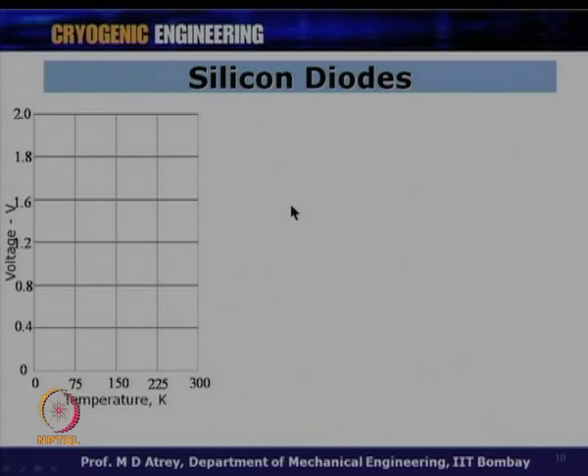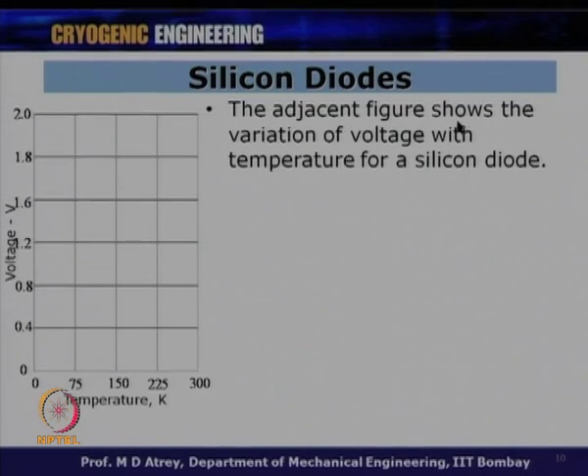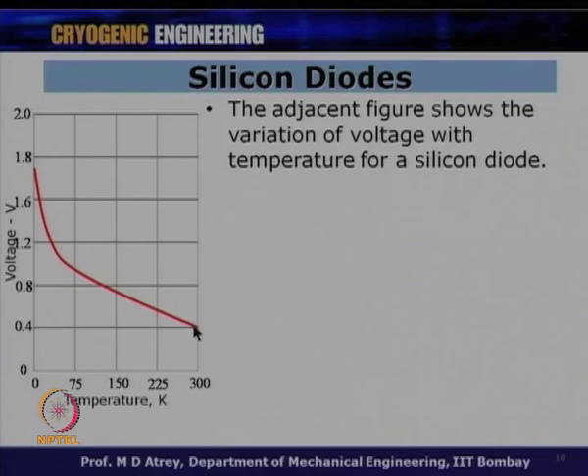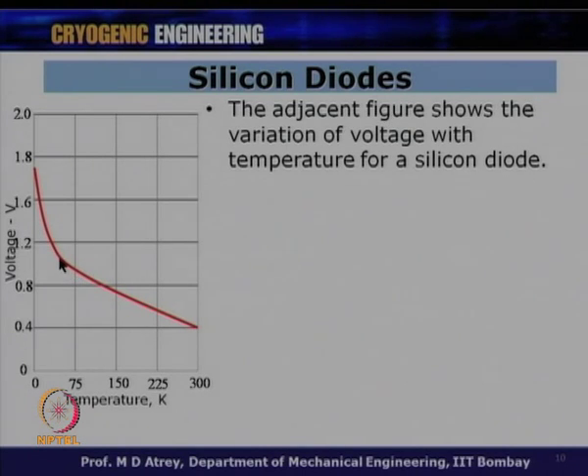The adjacent figure shows the variation of voltage with temperature for a silicon diode, with voltage on the y-axis and temperature on the x-axis. Unlike PT100 where voltage decreased with decreasing temperature, in silicon diodes voltage increases as temperature decreases — so sensitivity is negative. The response is linear up to about 50 Kelvin, and there is also good linear variation below 50 Kelvin, enabling a good calibration curve.